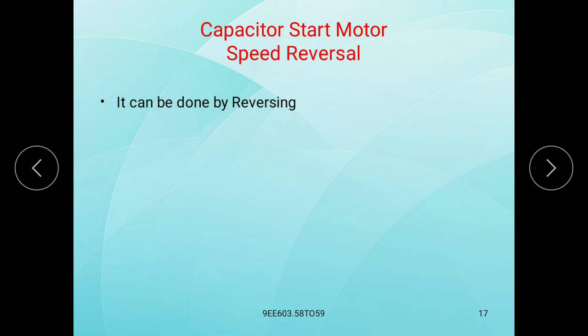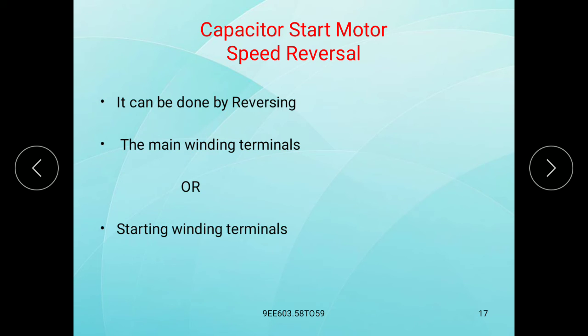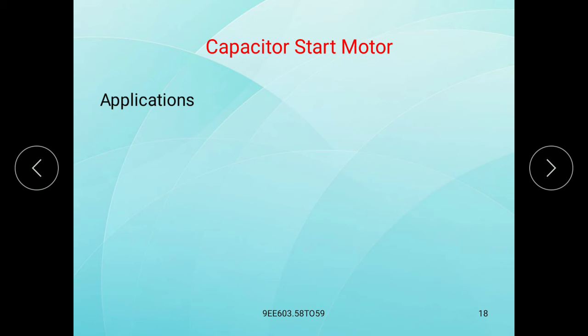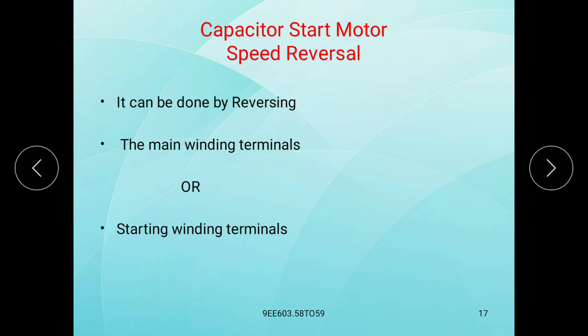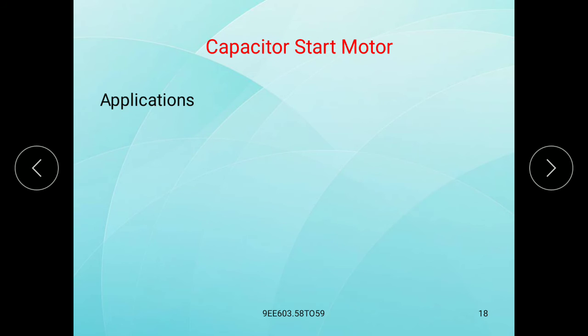The direction of rotation of the capacitor start motor can be reversed by reversing the main winding terminals or the starting winding terminals — one set of terminals should be connected in the reverse direction.